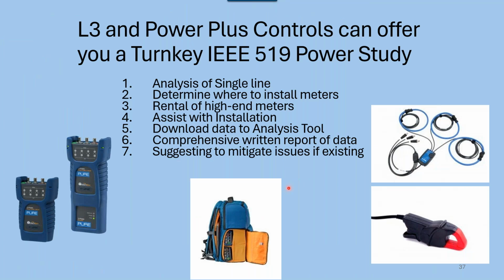The way we do this, Carlin Boswell made me add this slide. What we'll do is first analyze your single line diagram. Then we determine where to install the meters. Ideally, I'm going to put them at the PCC, point of common coupling. We can rent you the meters. We've got 13 meters, so we have more than you'll ever need. We're actually using this portable meter. It comes in this nice carrying case.